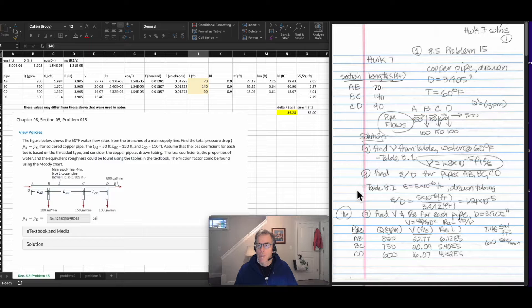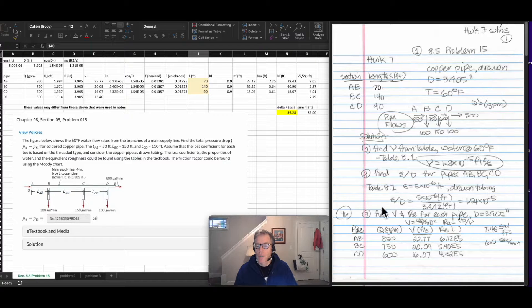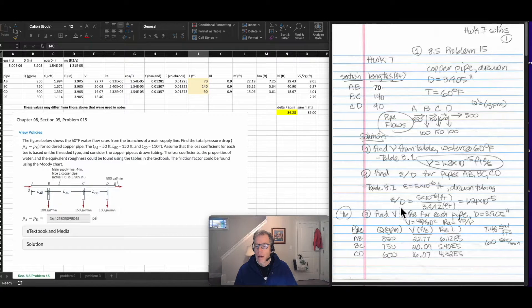Step two was to find the relative roughness for each of the pipe sections needed to calculate the major losses. I went back to the table and found for drawn tubing the value for epsilon: 5 times 10 to the minus 6 feet. I then divided by the pipe diameter, which I converted from inches to feet, and got this value for the relative roughness.